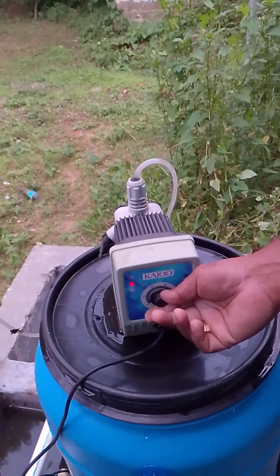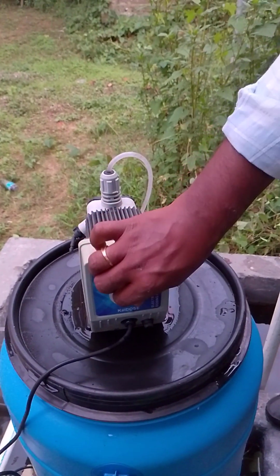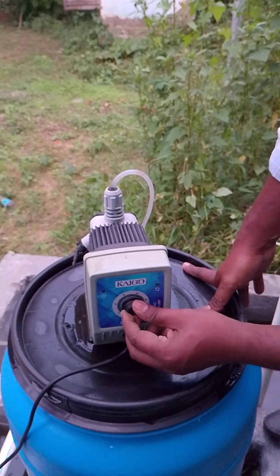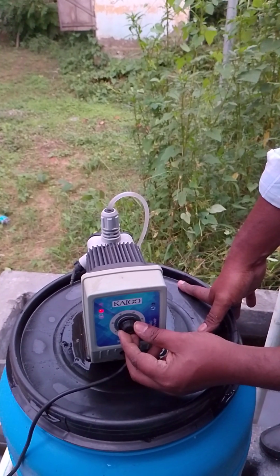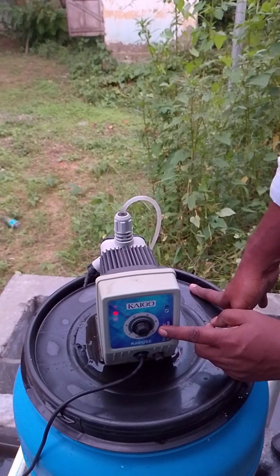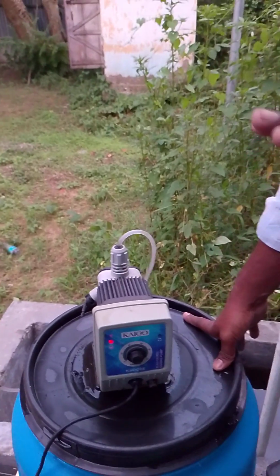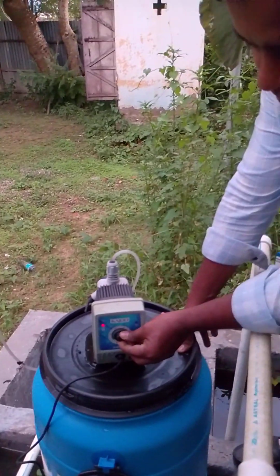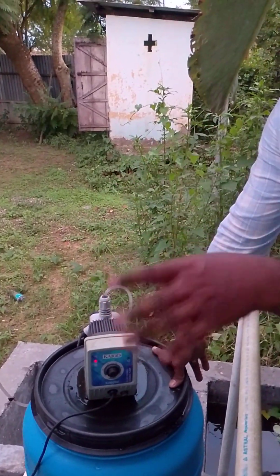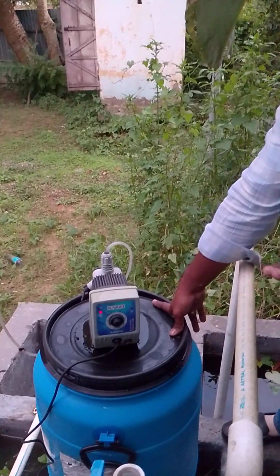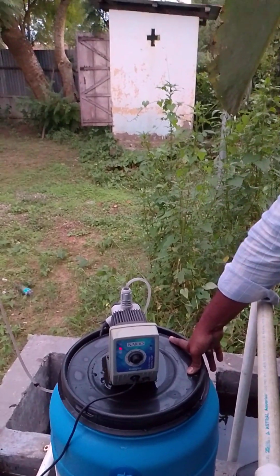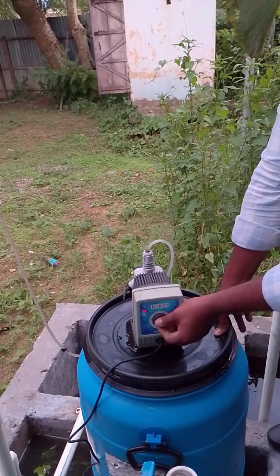So in the dosing pump, this rotary switch is there. Okay, so you can turn it off by rotating to the left side, anti-clockwise, and you can turn it on here. Whenever it is at 100, it will add 6 liters per hour of chemical in the pipeline. Okay, whenever it is 50%, it will add 3 liters per hour. This drum is designed for your chlorine chemicals. Okay, it will add the chemical for disinfection, and you have to run it according to your requirement.